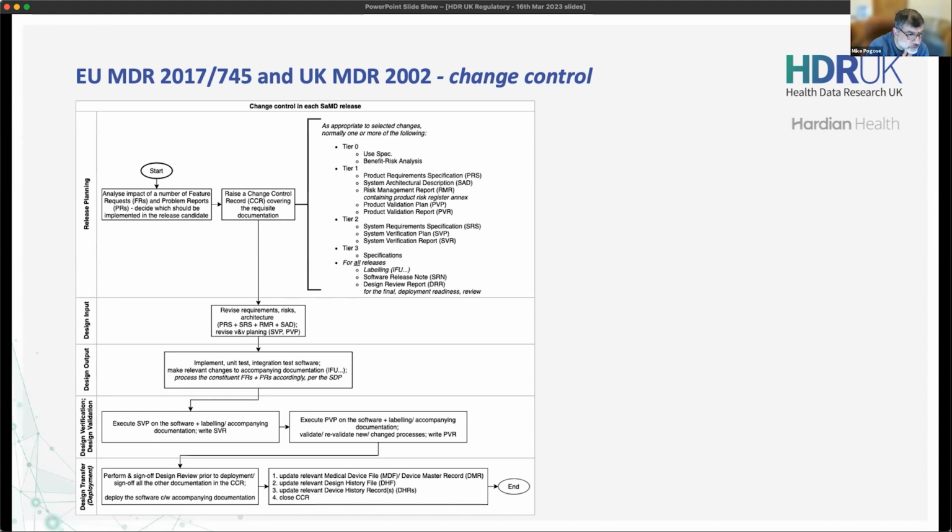So what if we do not replace the current language, but add a second language to the software? So that's a tier 1 change, potentially. Because I would say there's a validation of language comes in. So, clinical, technical language, let's be very silly, you do it through Google Translate, it comes out with hilarious things, but clinically and technically, are you actually really using the natural language in the proper way, using the terminology properly? So again, that's a tier 1 change because you cause potentially a validation that the instructions you give, can people still follow them in the same way that they did in your original language?